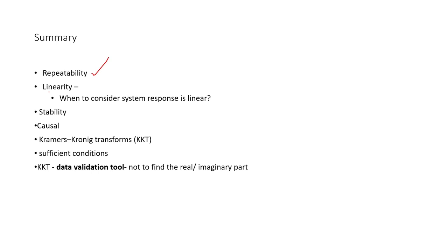1 to 10 millivolt, you have told. Yeah, okay, correct. So basically we go for 1 to 10, and we prefer 5 and 10 millivolt. So what does it mean? If we go lower than 1 millivolt or below, what do we see? The noise can play a bigger role, and in that case the signal to noise ratio will be poor, and the output that we get will have the effect of noise, which is not good. So in that region, less than 1 millivolt or so, the signal to noise ratio will be low, but still the system will be linear.